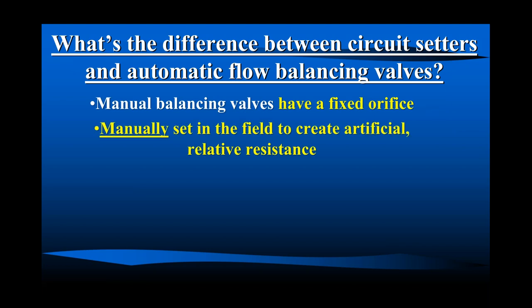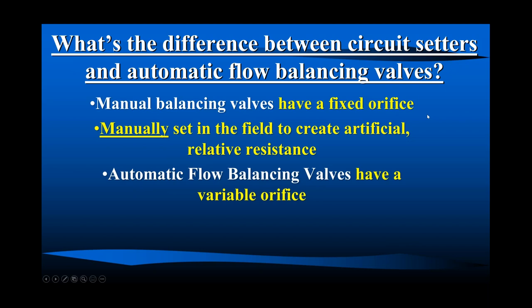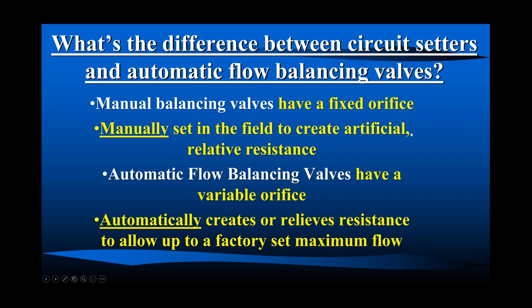Manually set, it's called a manual balance valve. You have to touch it in order to create artificial relative resistance. Automatic flow balancing valves have a variable orifice. Automatically, just like it says, you don't have to touch it in the field to create or relieve resistance, and it allows up to a factory set maximum flow. That maximum flow is your design day flow through that terminal unit, and it is factory set. That's why automatic flow balancing valves are also called flow limiters. So I'll use that term interchangeably with automatic flow balancing valves. They're the same thing. Flow limiters, automatic flow balancing valves.